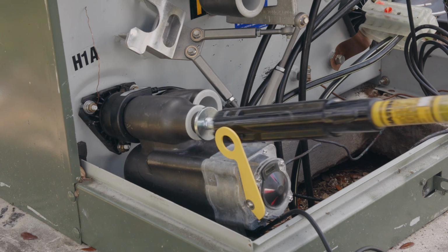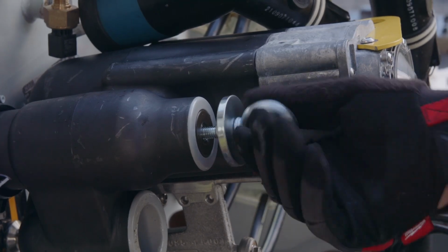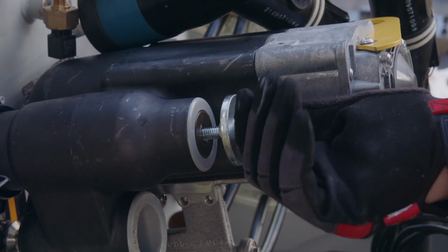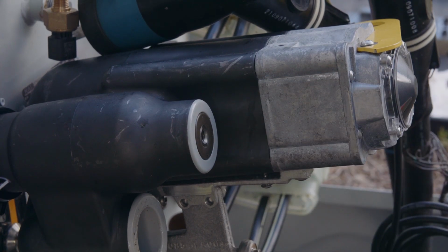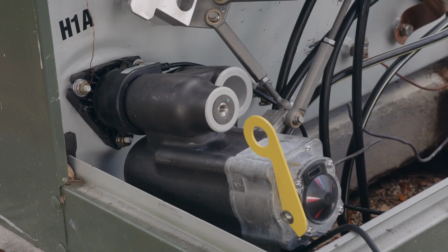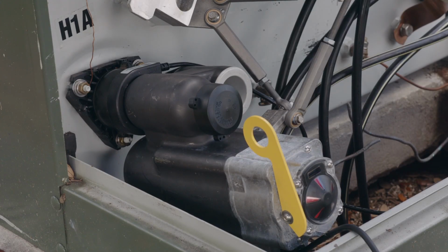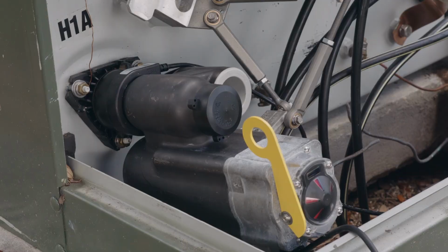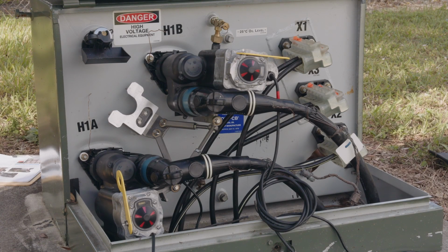The plug should be flush with the opening in the bushing well interrupter. Remove the plug install removal tool. Step 4. Install the plug cap over the plug on the H1A bushing well interrupter. The H1B plug and cap is installed the same as the H1A plug and cap.